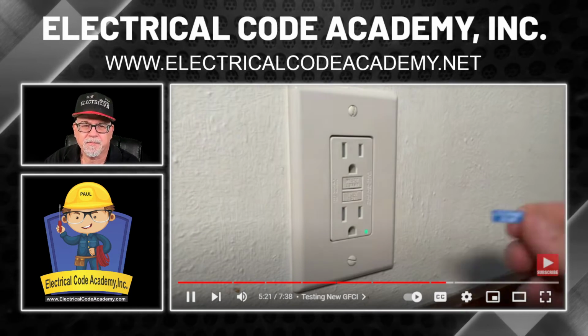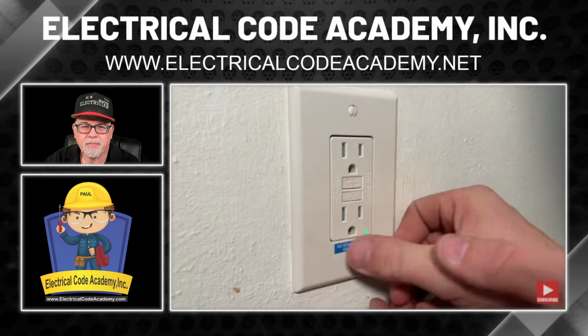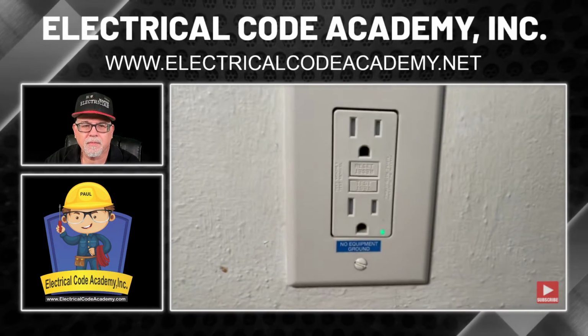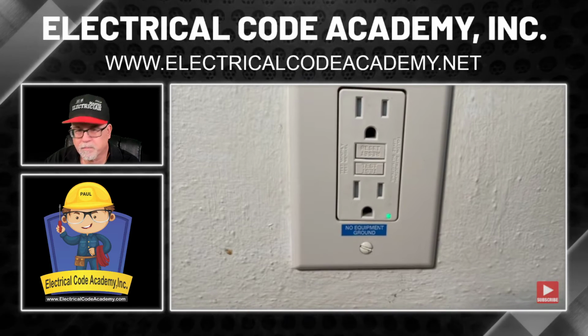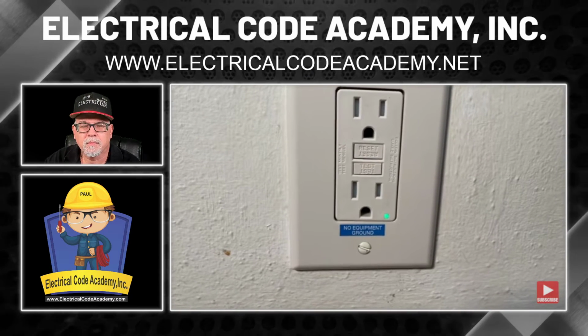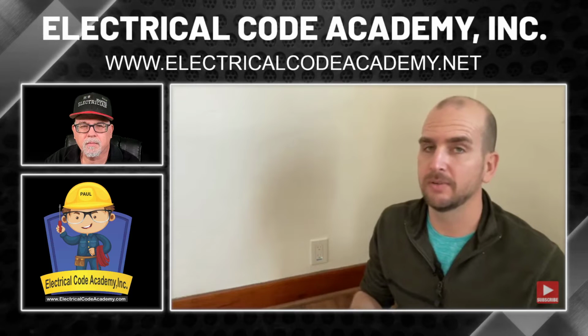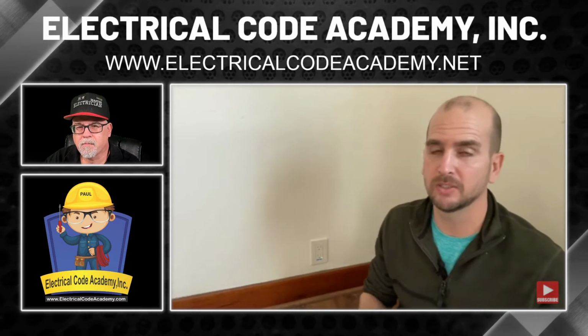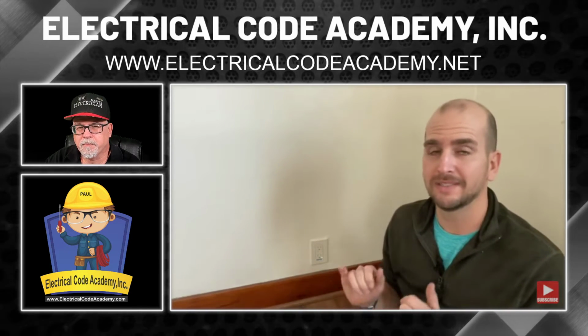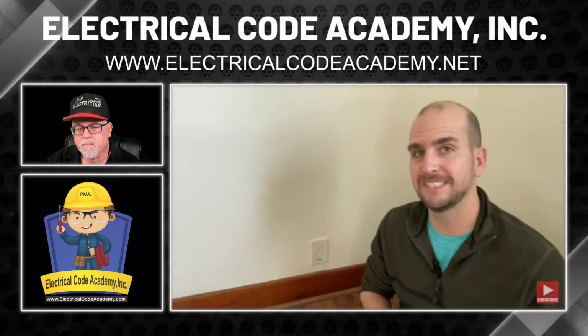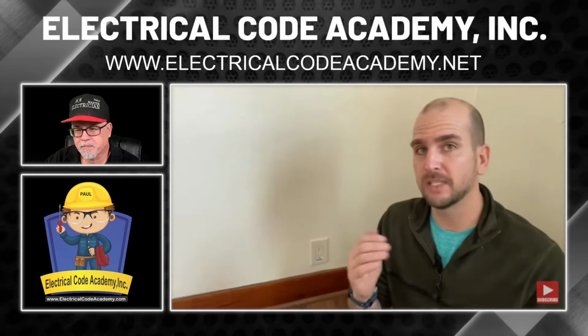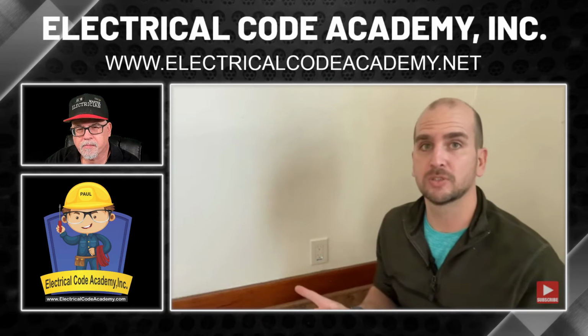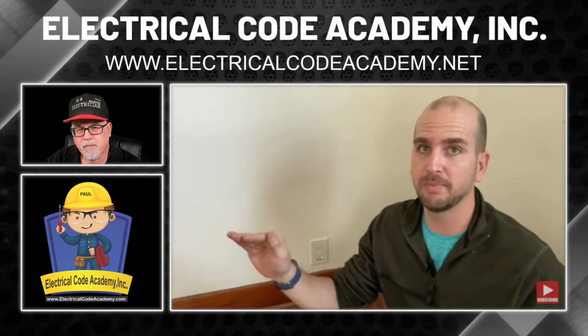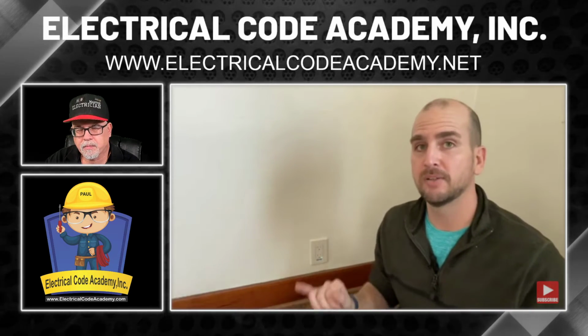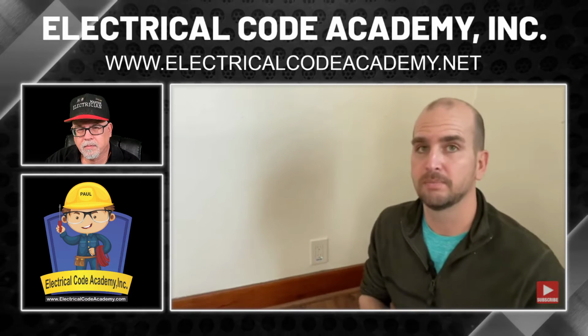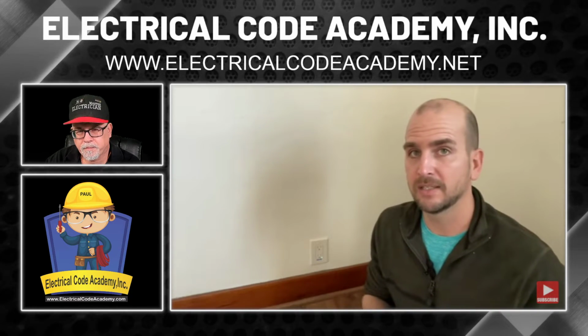Because of that, the NEC does call out that we need to label a no equipment ground sticker on the faceplate, and the sticker will be found in the GFCI box so you can use it. So not too bad, right? Something you knock out pretty quickly, and it's just so much more functional and safe to have this GFCI 3-prong. So if there is a fault there, this will actually trip. It doesn't have the ground return path, which isn't ideal, but if there is a fault, it will trip because of the design of the GFCI outlets.